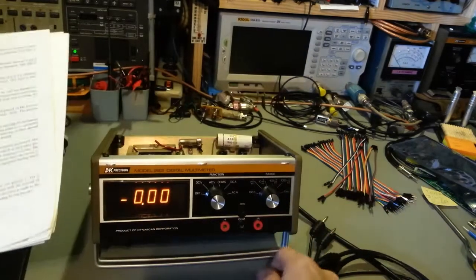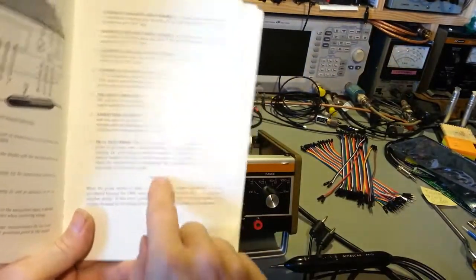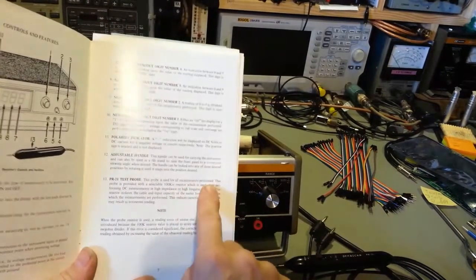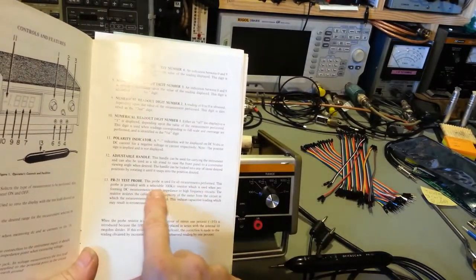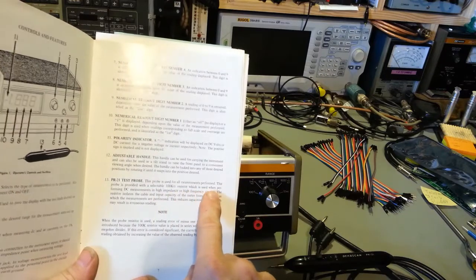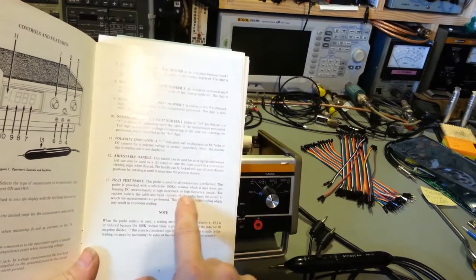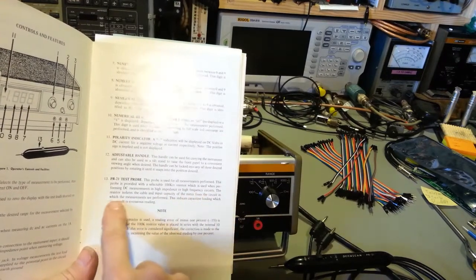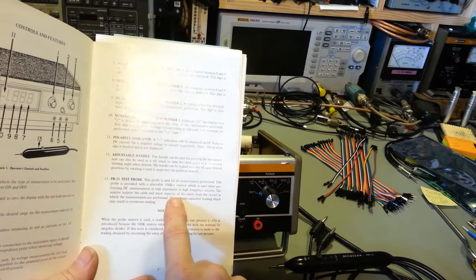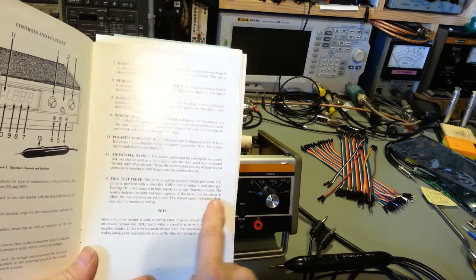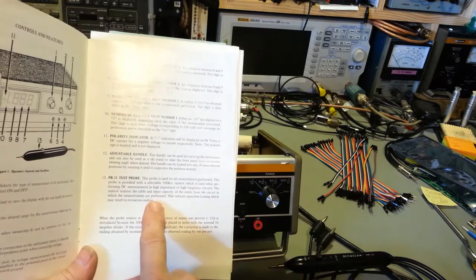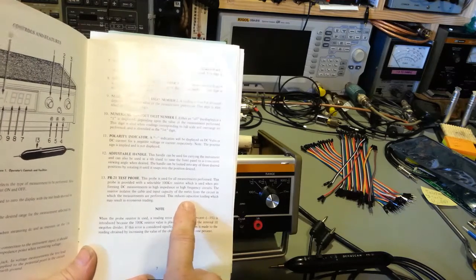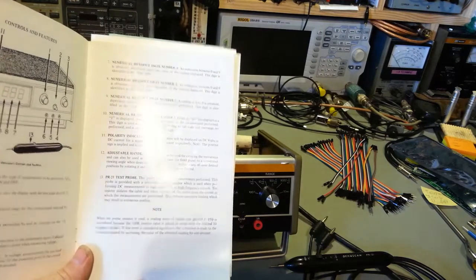As they describe it, this probe is provided with a selectable 100K resistor, used when performing DC measurements in high impedance or high frequency circuits. The resistor isolates the cable and the input capacity of the meter from the circuit being measured, which reduces capacitive loading that may result in erroneous readings.